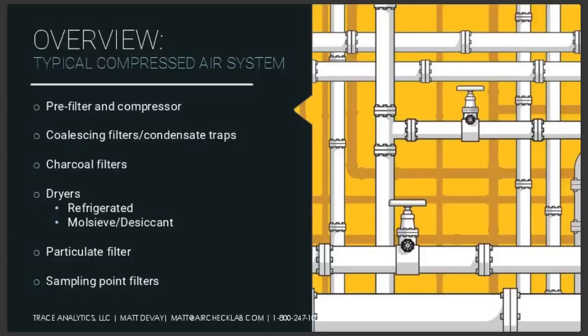A lot of you probably use refrigerated dryers. Some of you might have molsieve or desiccant. But these both are the same in that they remove water out of the air. After drying, typically there's a first pass particulate filter that can remove anything that might be introduced in the drying step, particularly if you've got desiccants.